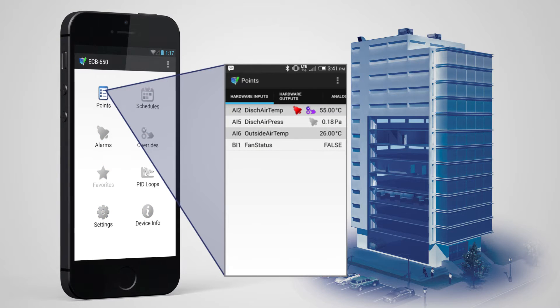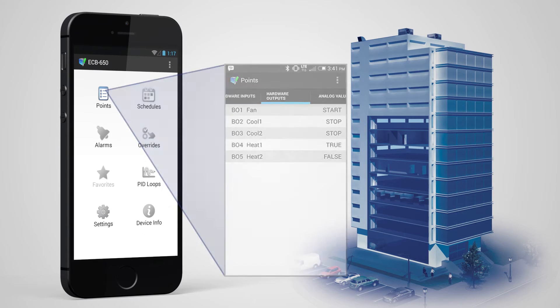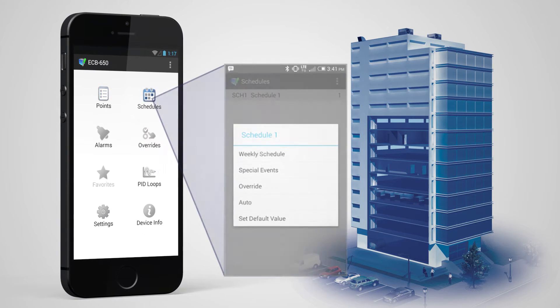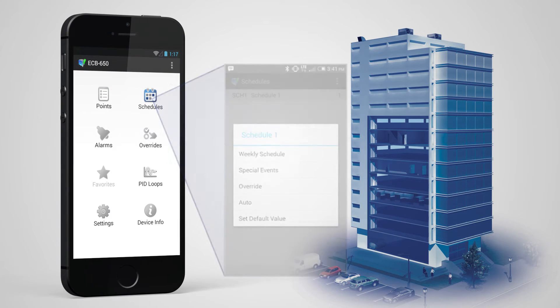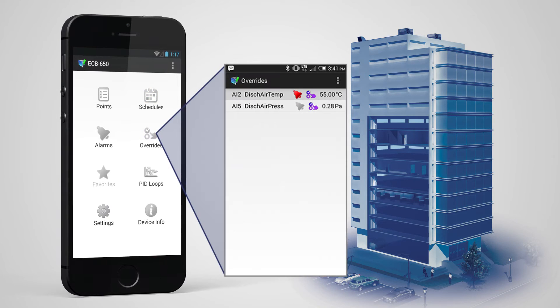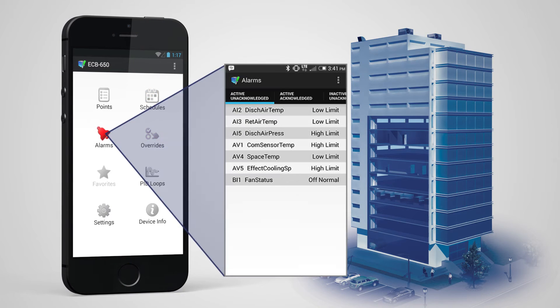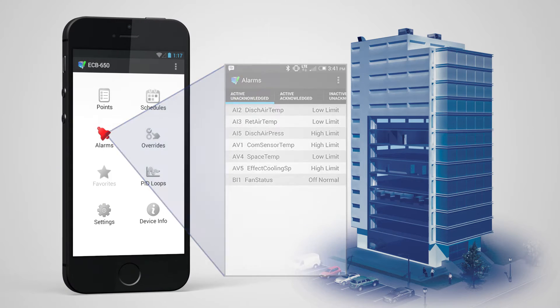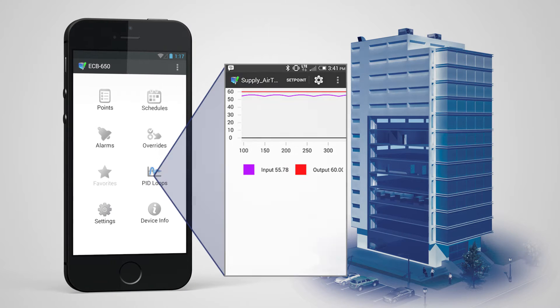Using MyDC Control, you can quickly view and configure inputs, outputs, and set points. View and configure calendars and schedules. View points, change their value, or remove overrides. Monitor your list of active alarms and take the proper actions when required. Configure the controller's PIDs and view real-time system response graphing.